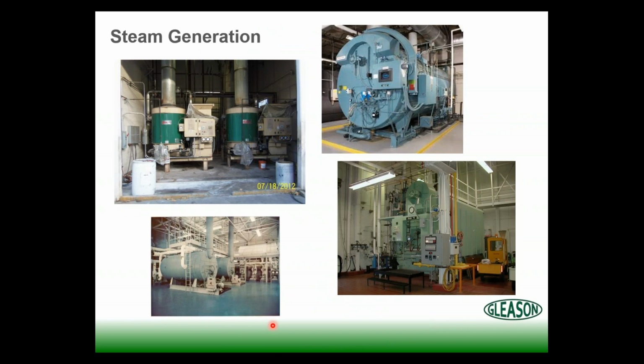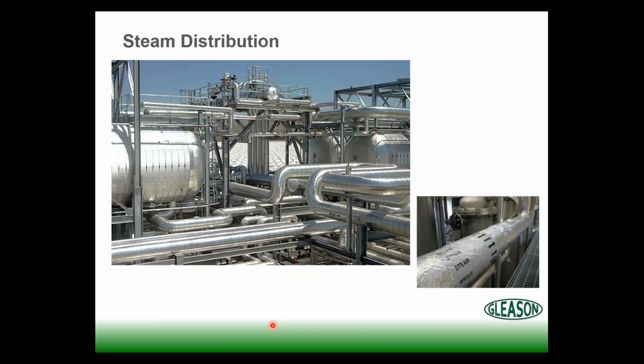So here's just some different boilers. We're not talking about boilers today, but just different styles of boilers that fit depending on what our needs are on the generation side of things. And then steam distribution. We can transport steam a very, very long way successfully. We don't necessarily have to superheat it. We just have to pipe it properly and steam trap it properly.